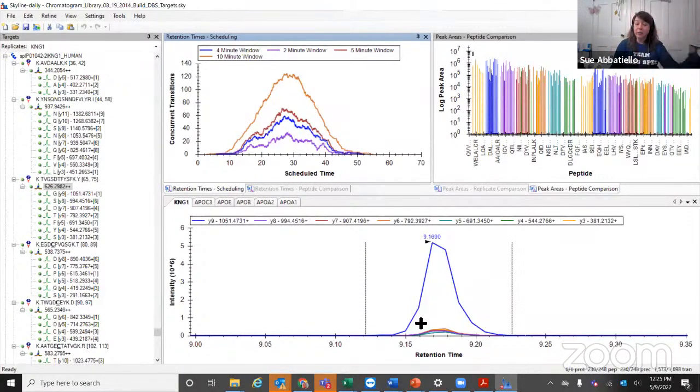Once you have a high number of peptides to target, like 100 or 1,000, your instrument is going to spend so much time in a given cycle on peptides that are not actively eluting, and you might only get a couple of points across your peak. For argument's sake, let's say it takes 10 milliseconds for each of these transitions. The more you have, the more time it's going to spend in a given cycle. So what you do is you schedule your peptides.